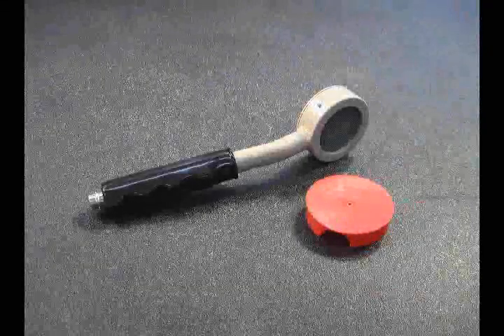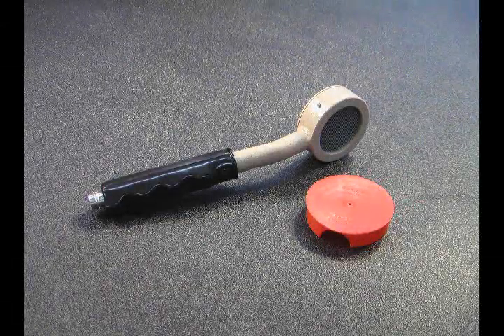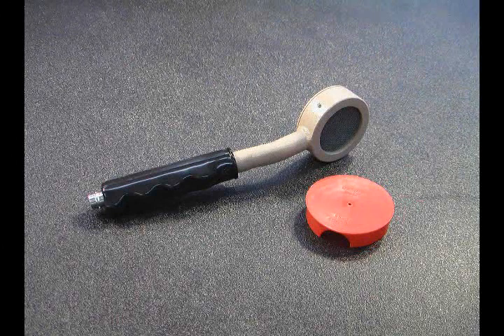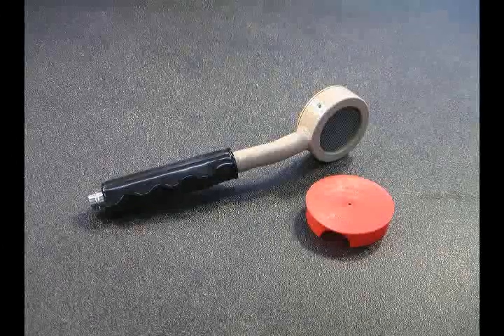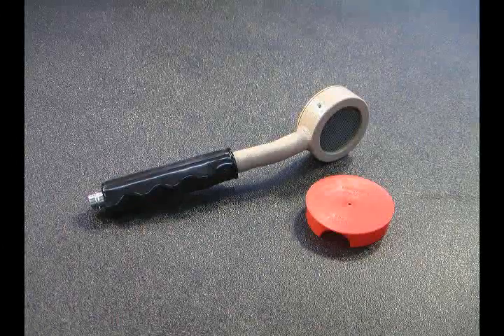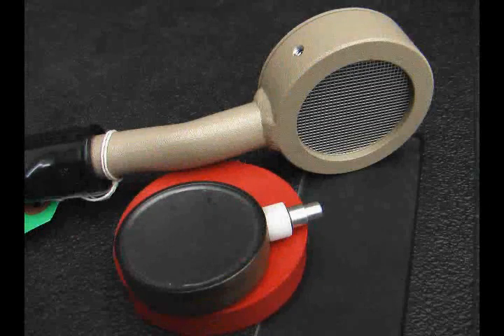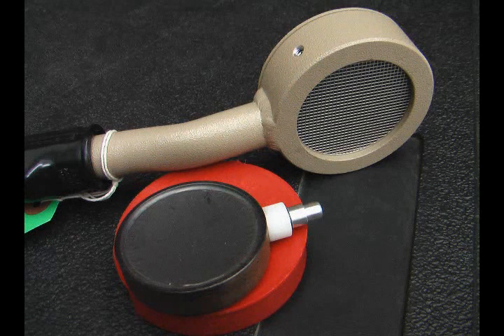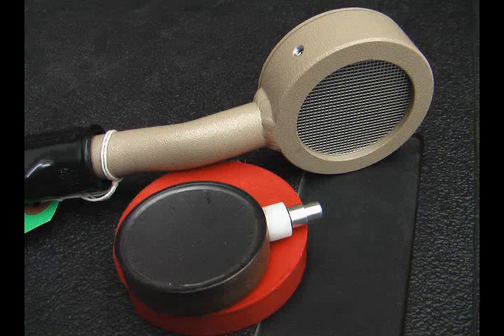The Model 44-9 pancake detector will detect alpha, beta, and gamma radiation. Its size and shape provide easy handling for surveying or personal monitoring. It contains a tube filled with halogen-quenched gas and has a thin mica window. The thin mica window is protected by a stainless steel screen.